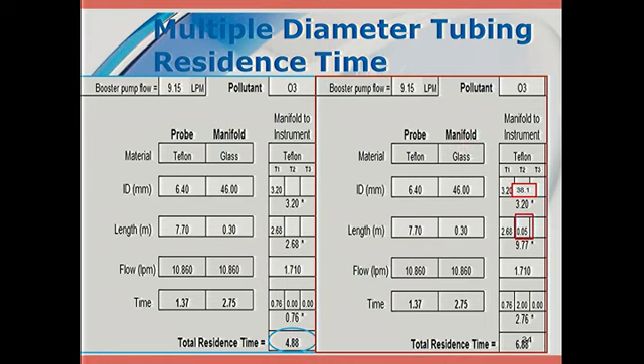So that's what we added with the two new little blocks. And even if you had a third, let's say you changed your Teflon line between the inline filter holder and the back of your instruments, there's room for 3 different multiple diameters. And again, this is our new calculation.